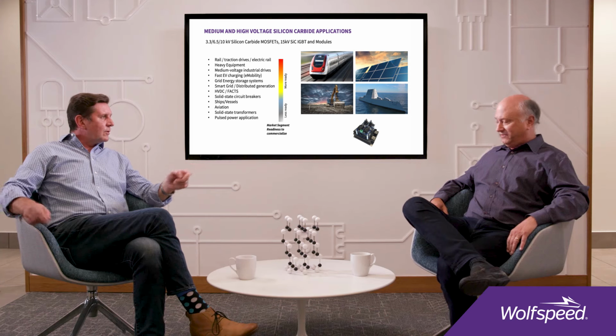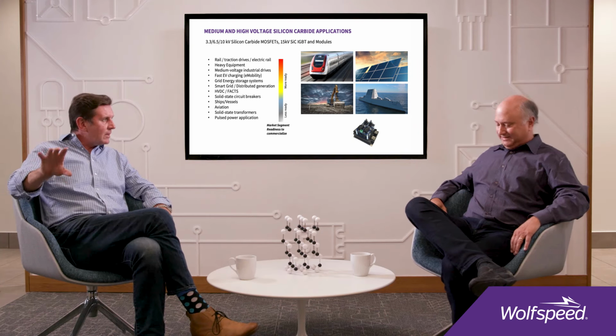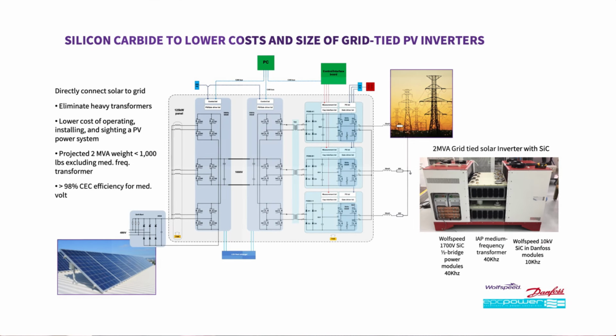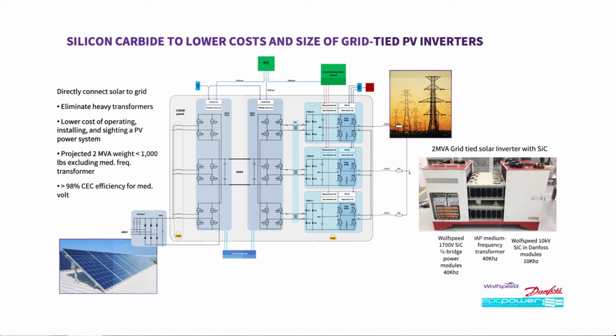You have a solid state, or high frequency, transformer, and on the low side we were feeding out to what would be a solar grid array at 500 volts DC. So 13.8 down to 500 volts, and DC - the important bit is DC. So DC coupled, we're doing both the solid state transformer and the AC to DC conversion. That's been very successful.